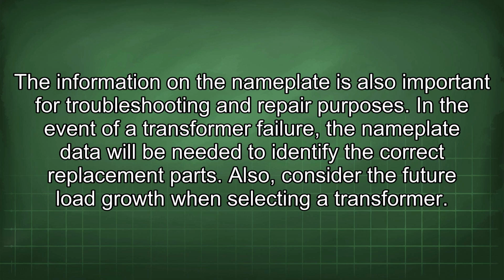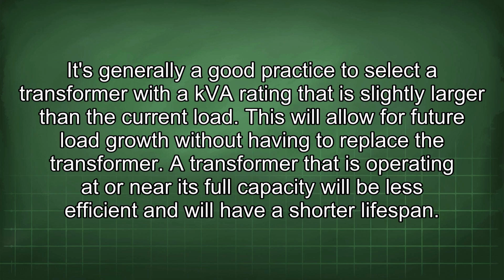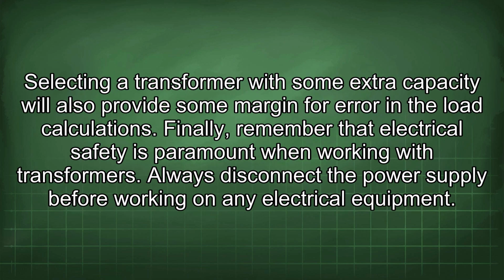Also, consider the future load growth when selecting a transformer. It's generally a good practice to select a transformer with a kVA rating that is slightly larger than the current load. This will allow for future load growth without having to replace the transformer. A transformer that is operating at or near its full capacity will be less efficient and will have a shorter lifespan. Selecting a transformer with some extra capacity will also provide some margin for error in the load calculations.